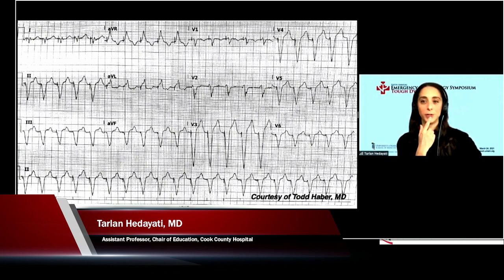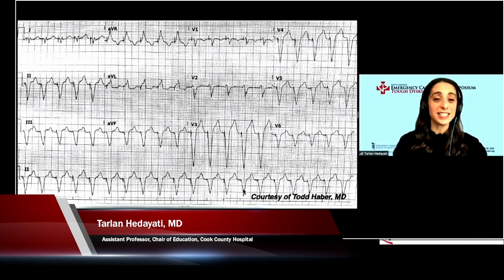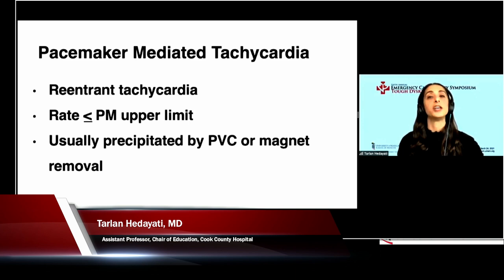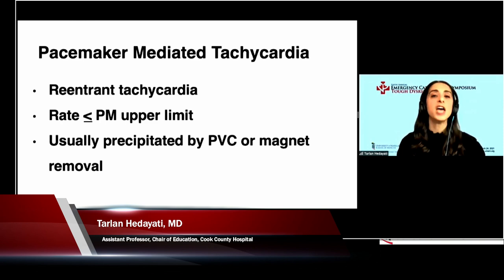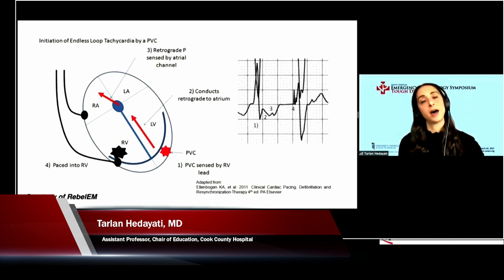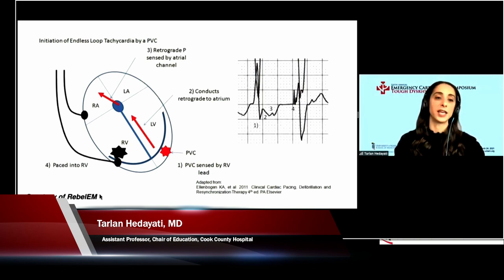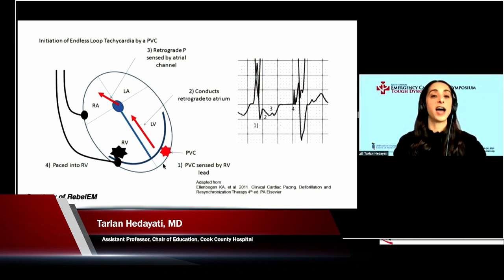What happens with pacemaker-mediated tachycardia is that the pacemaker is part of a reentrant tachycardia. The good news is that the rate will never exceed the upper limit of the pacemaker, whatever that's set at. It's usually precipitated by a PVC or by putting a magnet on a patient and then removing it. If that happens, just put the magnet back on the patient again. This schematic shows a PVC firing, getting conducted up towards the atrium, and that retrograde P is sensed by the atrial channel, which then shoots it down again to pace the RV again. So you get this reentrant tachycardia that the pacemaker is a part of.